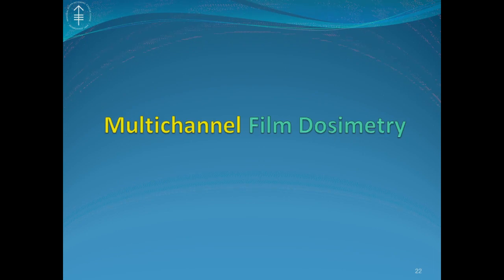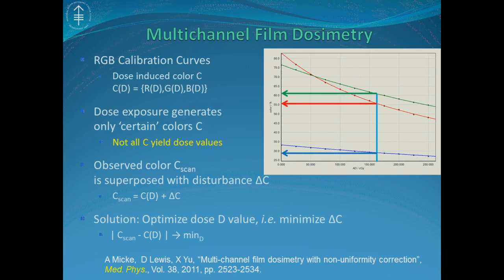So what is multi-channel film dosimetry? Use of all three color channels allows for the separation of the scan signal into one part that is dose dependent, C sub D, and another part that is dose independent, delta C. This enables the correction for disturbances in the digitized image, including non-uniformities in the film, as well as scanner-related artifacts.